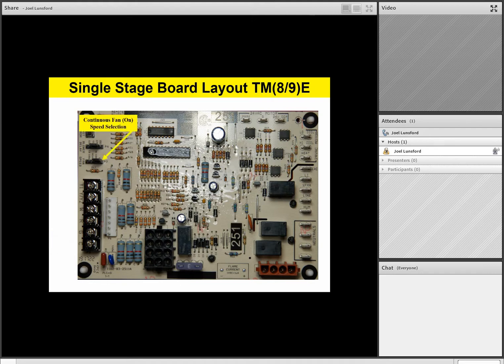The first one we're going to talk about is our continuous fan on speed selection. It should be noted that this is a very unique feature about the Champion Johnson Controls furnace control, in that we're going to give you some options of what speed you want the fan to run on if the homeowner goes to the thermostat subbase assembly and selects fan on. That jumper allows that. You'll notice that we have high cool, heating mode, low cool, or just G. And G, again, will be selected by determining our 24 volt input to the board.